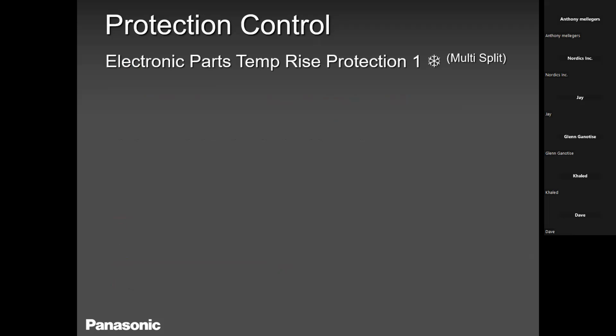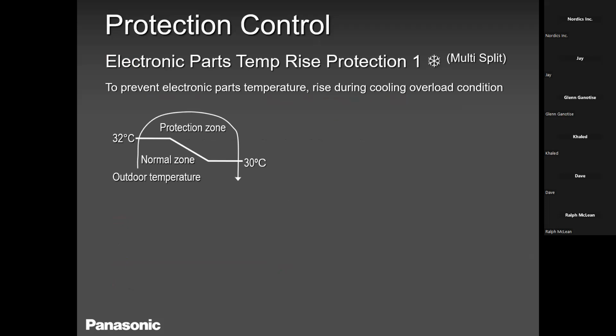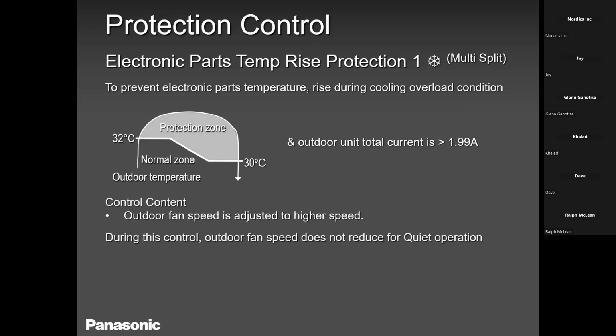So electronic parts temperature rise protection was always there from before. Basically, in a nutshell, all it does is increase the outdoor fan speed when those components are getting a little bit hot, maybe because of poor air circulation, maybe the coil is dirty, maybe the fan is not moving the way it's supposed to, and they get hot. So the outdoor fan will increase its speed and try to get rid of the higher temperatures from each and every component out there. That's what electronic parts temperature rise protection is all about.